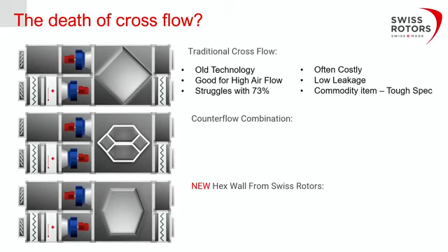They're often very costly, Crossflow units, because they're very heavy, they're very big, and they're often made from aluminium only as well. So they're often very costly. They're very good for high airflows though, because you can moderate the plate spacing that you would get between each layer. They offer a very low leakage, the same as we do with a HexWall, but they do struggle in today's world with 73%. You do have to make them quite big, and whenever you make something quite big, you also make it quite expensive. And it's a commodity item.